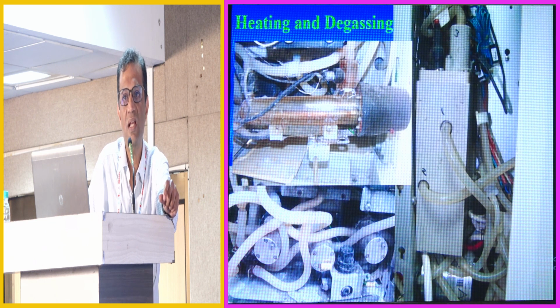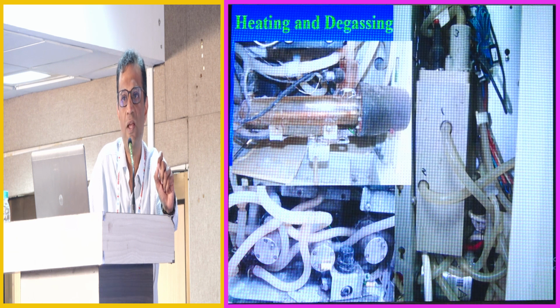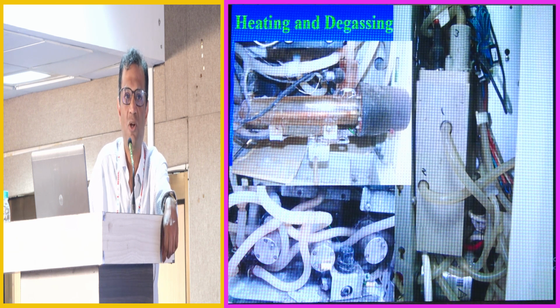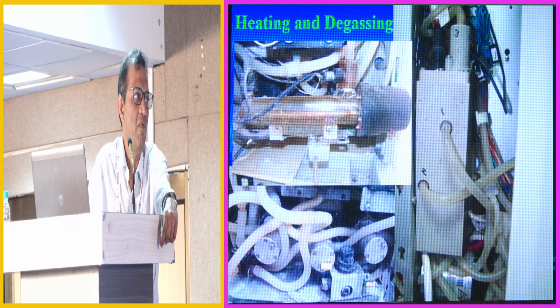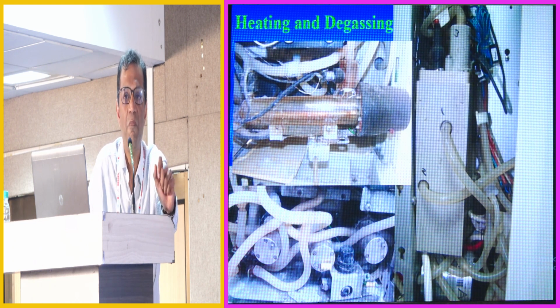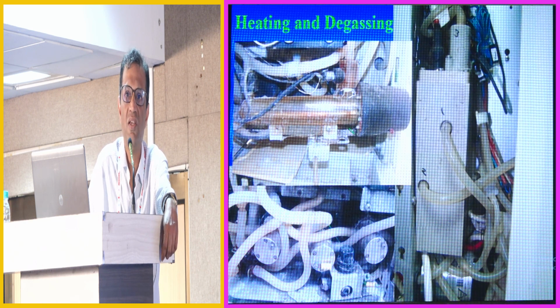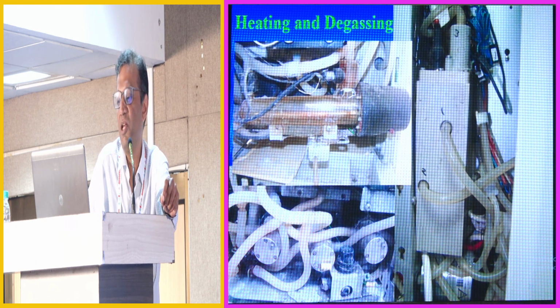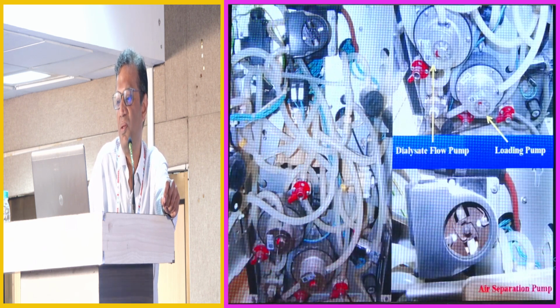This black knob over here is the adjustment of the inlet water pressure. Remember that while you may increase the pressure by turning the knob clockwise, it cannot raise the pressure above that of the line pressure. Dialysis machine manufacturers will tell you the minimum pressure that the machine must receive. It's about 0.7 bar or 10 psi for the Althin machines, about 1 to 1.3 bars for Fresenius machines and 1.5 to 2 bars for the Gambro AK series machines. So your line pressure must be at least 2 bars of pressure, and then you can adjust the pressure coming to the machine with the help of the knob.